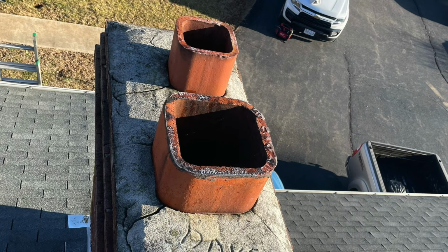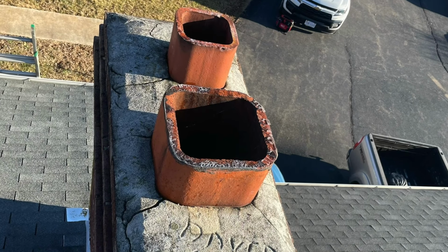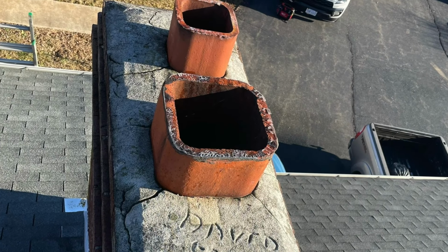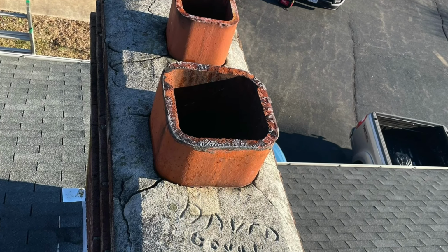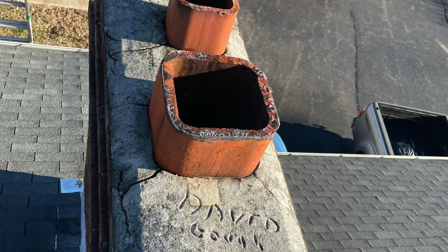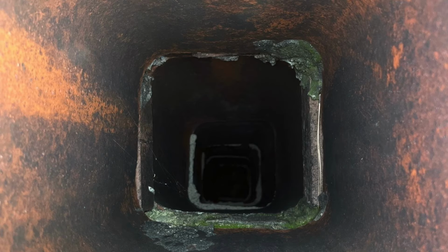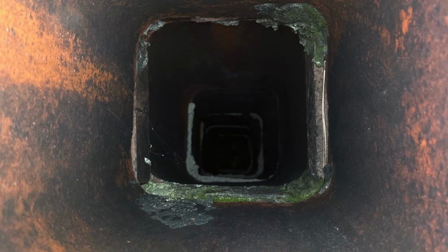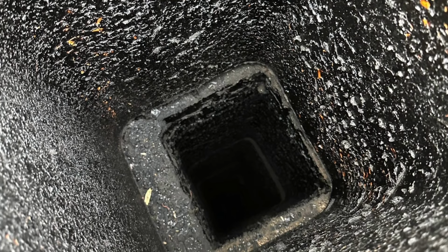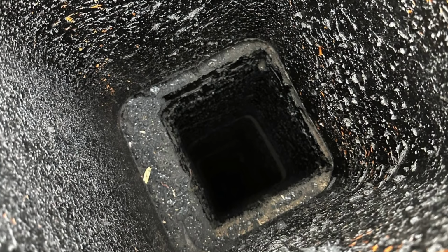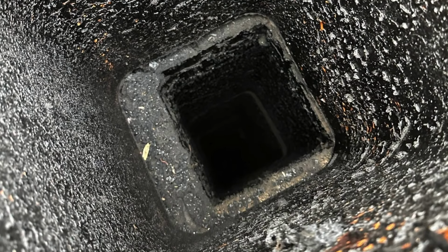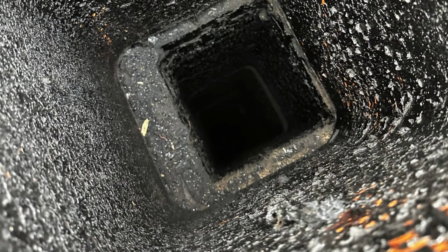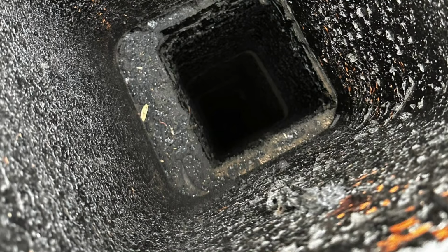At the same time, the flue tile should not extend more than 4 inches above the crown. When too much liner is left exposed, the surrounding cold air cools the flue gases rapidly as they enter the exposed section of tile. This cooling slows draft, encourages condensation, and leads to the formation of creosote. Over time, excessive creosote accumulation increases fire risk and reduces system efficiency.